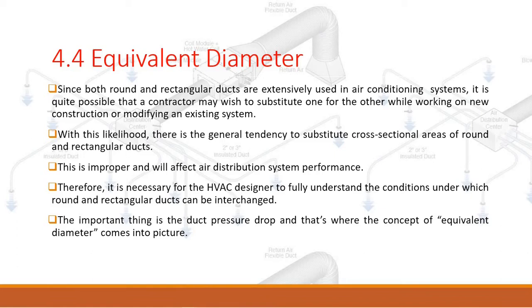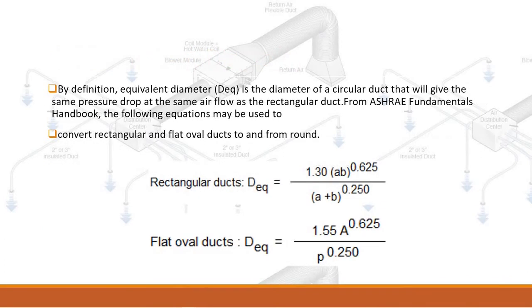The important thing is the duct pressure drop, and that's where the concept of equivalent diameter comes into picture. By definition, equivalent diameter is the diameter of a circular duct that will give the same pressure drop at the same airflow as the rectangular duct. From the ASHRAE Fundamentals Handbook, the following equations may be used to convert rectangular and flat oval ducts to and from round.